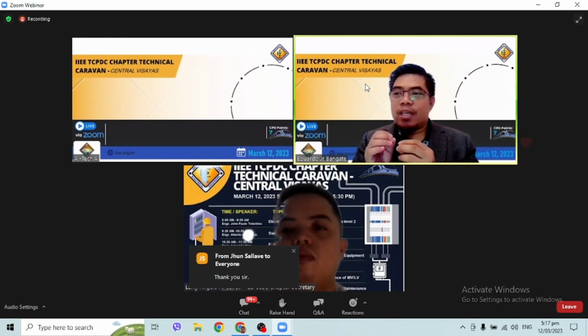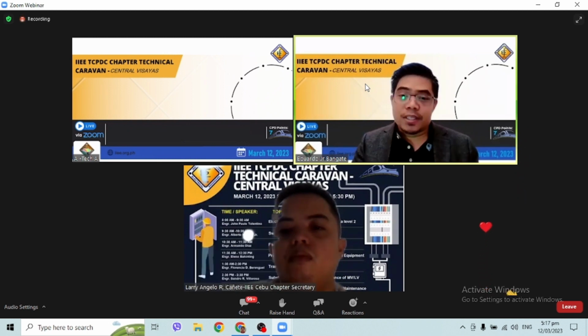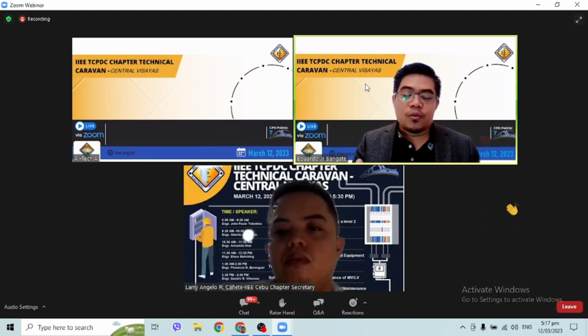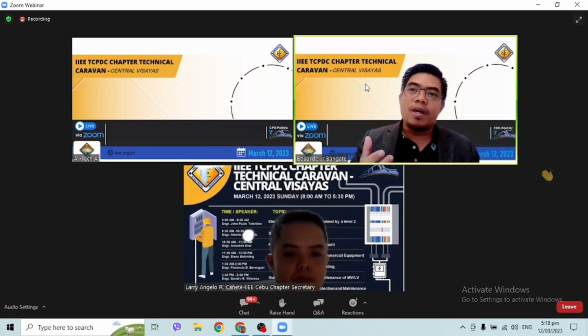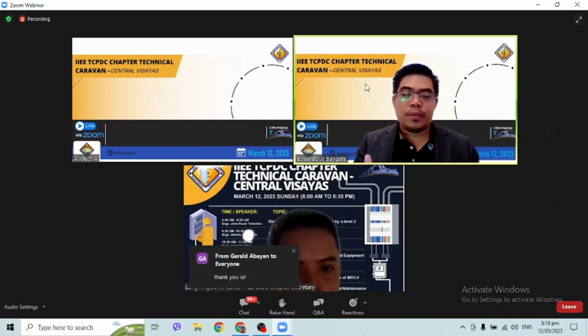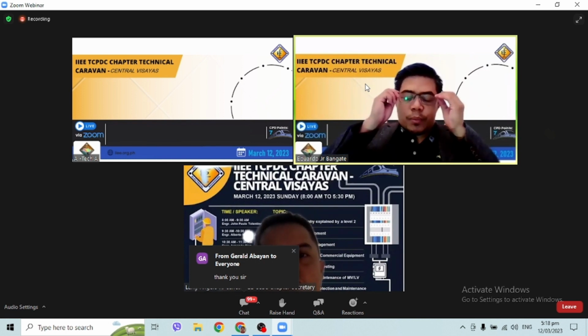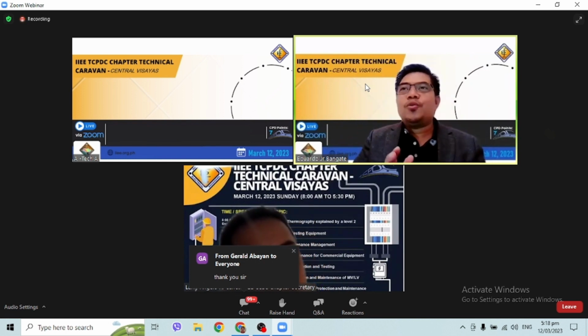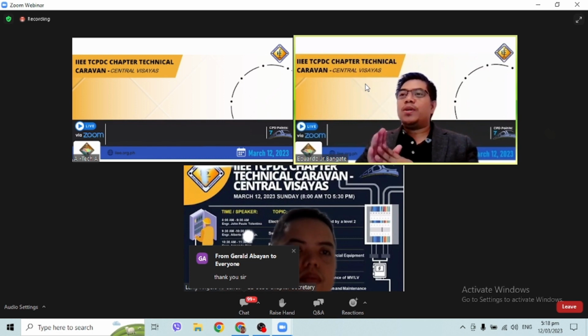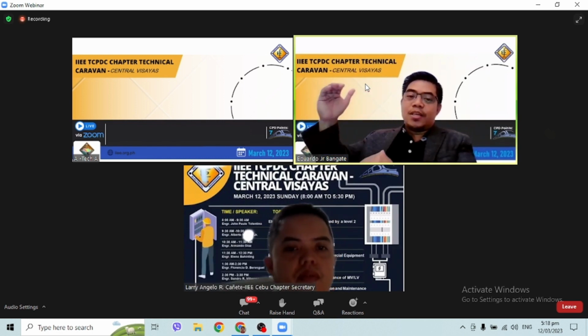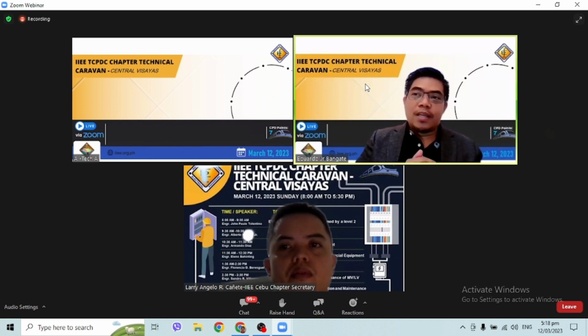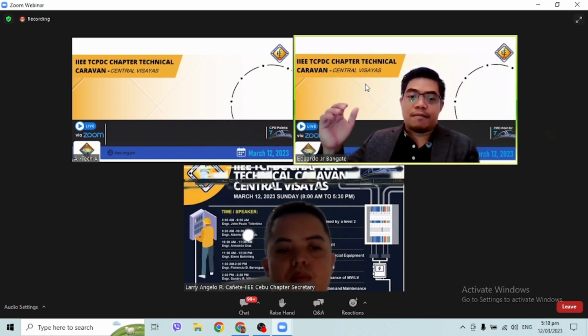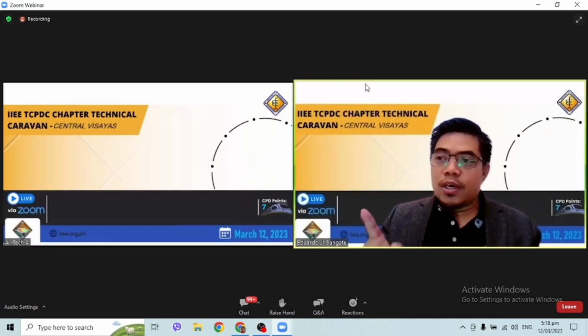Kasi meron tayong yung tinatawag na harmonics. So it means that the current draw will be higher. And if the requirement of the generator is based on what loads are available, then we can compensate. Because, for example, if you are a design engineer and you already know that your load is going to be like this, then you have to order a type of generator that will compensate the type of load that you have.